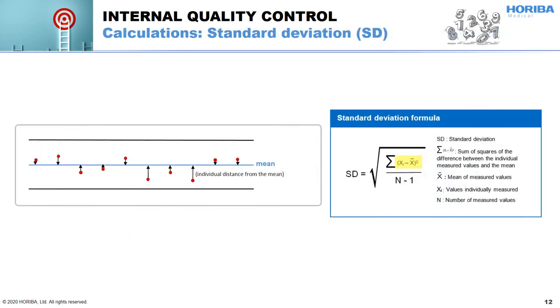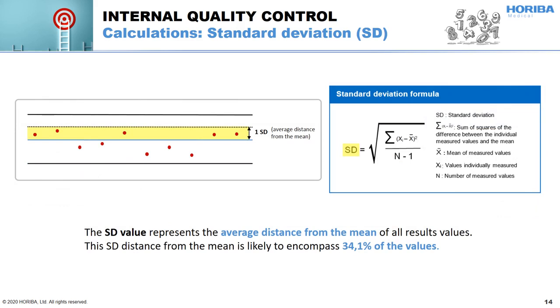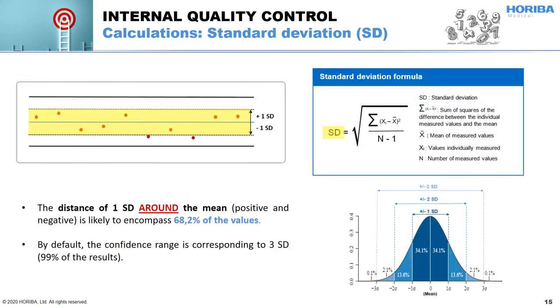To calculate its own standard deviation, the laboratory will start by running the control sample several times. Then it will measure the differences between all individual results and the mean. All those individual differences will be summed together. This sum will then be divided by the number of results minus 1. After making the square root of the previously obtained value, you will have the value of 1 SD. This gap to the mean includes 34% of the results. Taking ±1 SD around the mean will include double, so 68% of the results. By default, the confidence range is equal to ±3 SD, including 99% of the results.